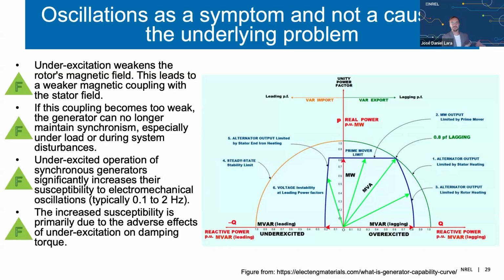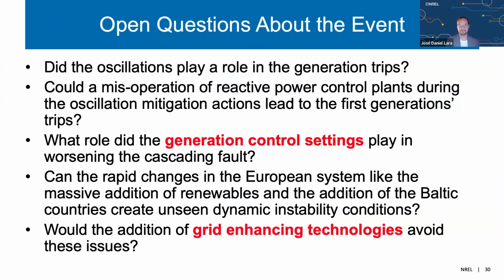And what was the second oscillation that we saw in the system? It was 0.22 hertz. It's almost like a textbook case of a system that has not required renewable generation to actually provide voltage regulation and is relying on synchronous machines, forcing them to operate at a risk of causing oscillations and increasing the susceptibility to adverse effects of under-excitation on the damping torque. And we saw that already happening in the previous slide: in January, when the nuclear power plant tripped, it was because it was operating in an under-excited regime.